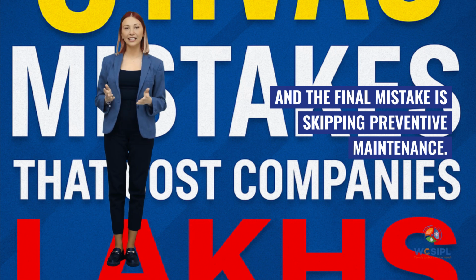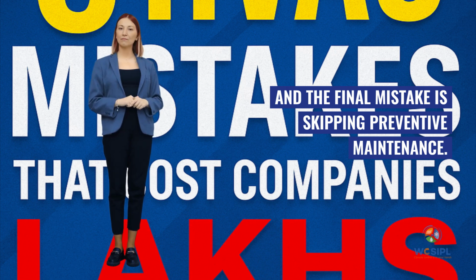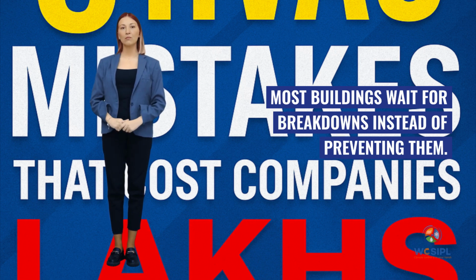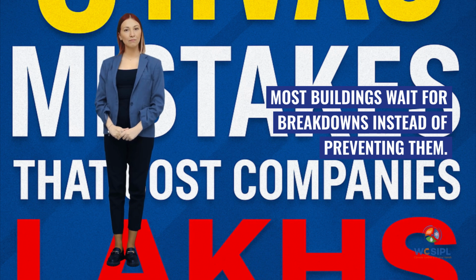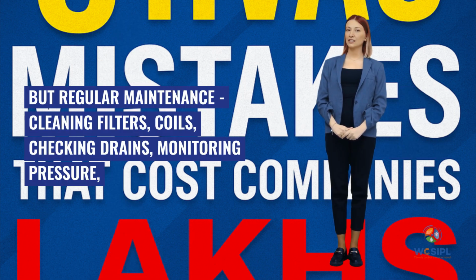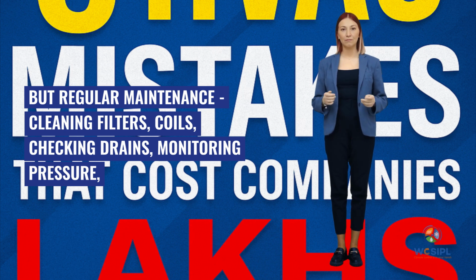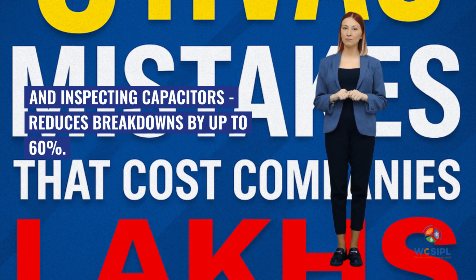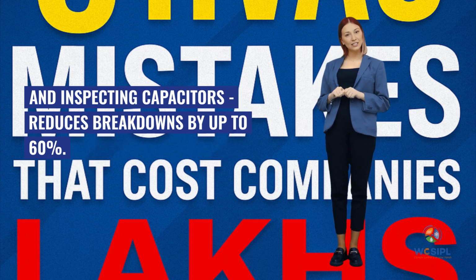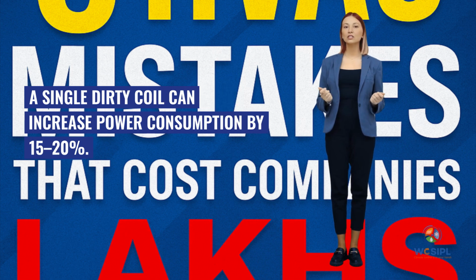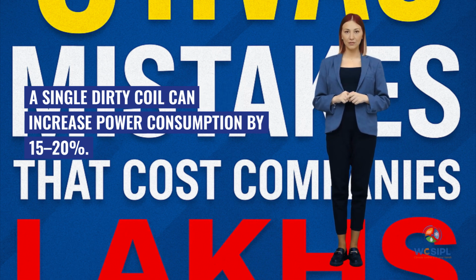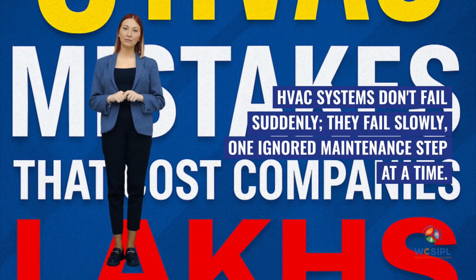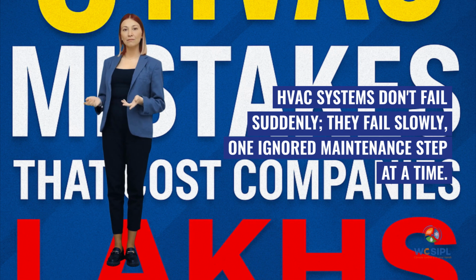And the final mistake is skipping preventive maintenance. Most buildings wait for breakdowns instead of preventing them. But regular maintenance, cleaning filters, coils, checking drains, monitoring pressure, and inspecting capacitors, reduces breakdowns by up to 60%. A single dirty coil can increase power consumption by 15 to 20%. HVAC systems don't fail suddenly, they fail slowly, one ignored maintenance step at a time.